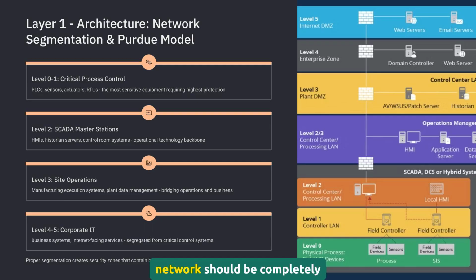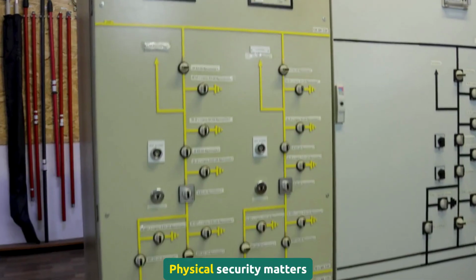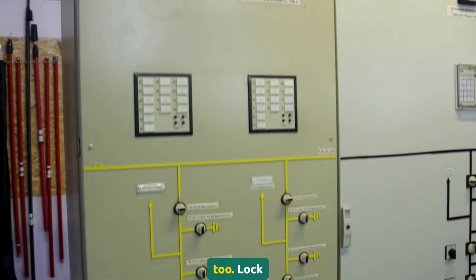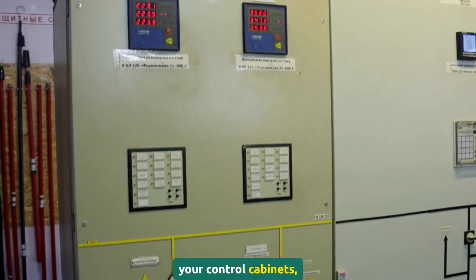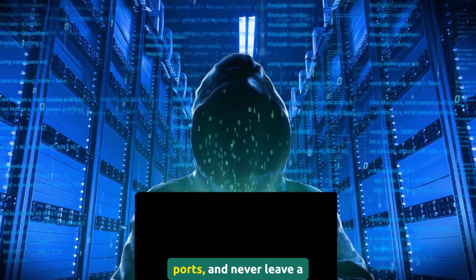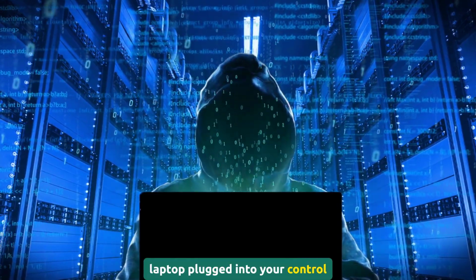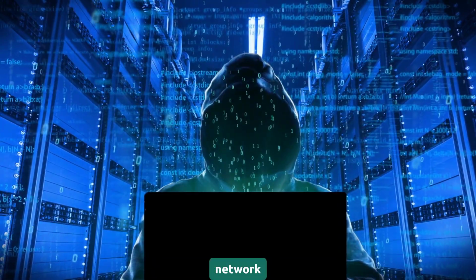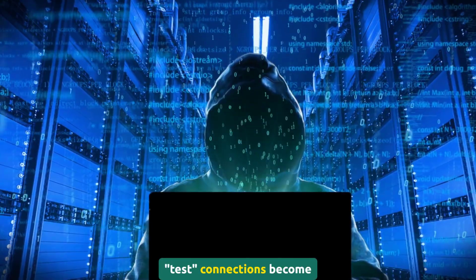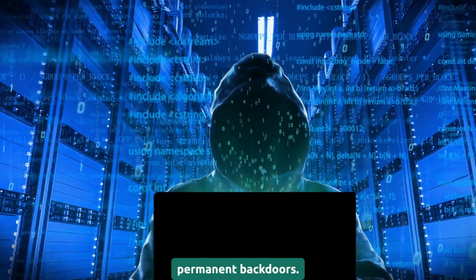Your PROFINET network should be completely separated from your IT network by a properly configured firewall. Not just a switch, not just a different VLAN, a real firewall with strict rules. Physical security matters too. Lock your control cabinets, disable unused switch ports, and never leave a laptop plugged into your control network unattended. I've seen too many test connections become permanent backdoors.